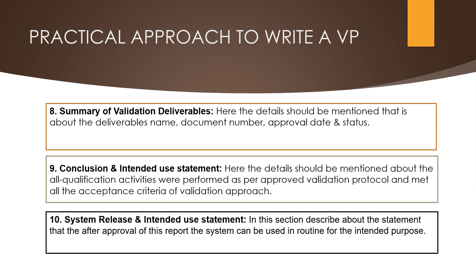The tenth component is the system release and intended use statement. In this section, the statement should mention that after approval of this report, the system can be used in routine for the intended purpose. It is also certified that the system has been successfully validated as per the approved validation protocol, regulatory requirements, and in-house procedures.